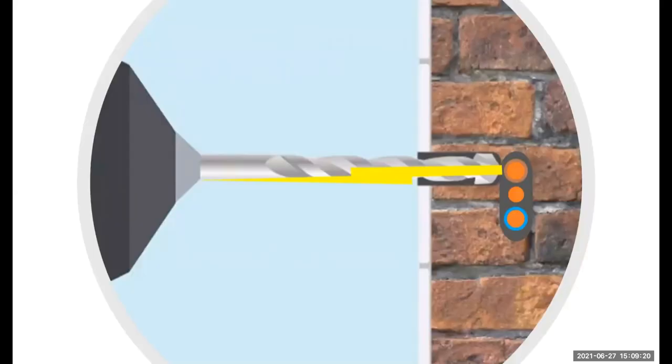So here's a typical example. You drill in. Most drills are double insulated, but you could touch the drill bit, damage the cable or screw you insert, and it becomes live. In this instance, you're relying on the 30 milliamp RCD for protection to pick up the imbalance of the load. What works best is down the CPC or between the live conductors, which would be here and here, without actually coming out of the wall.